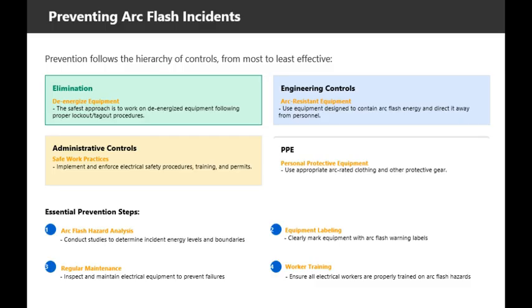Next are engineering controls, such as arc-resistant equipment. This equipment is designed to contain arc flash energy and direct it away from personnel. While this doesn't eliminate the hazard, it significantly reduces the risk to workers. Administrative controls include safe work practices, procedures, training, and permits. These controls rely on people following procedures correctly, which is why training and reinforcement are so critical. Finally, we have personal protective equipment, or PPE. While PPE is essential when other controls aren't sufficient, it's important to remember that it's the last line of defense, not the first.